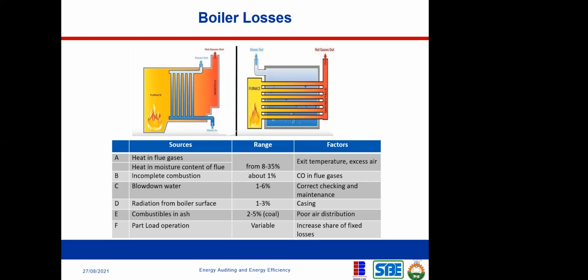and that's why we have the need for blowdown. We usually call it total dissolved solid blowdown. Okay, total dissolved solid (TDS). Okay, so we need to remove them, and that's the essence of blowdown water. So when you're blowing down those total dissolved solids, it also contains some amount of heat in that water that you're blowing down. You need to recover them. Okay, so what are the factors? Correct checking and maintenance. If you're doing your blowdown, you need to do a correct checking to make sure that you're not losing so much amount of heat in your blowdown procedures.